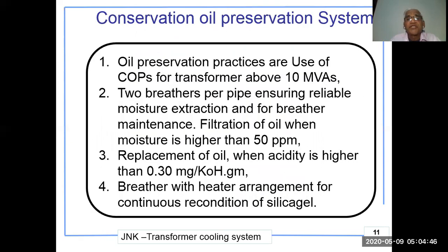Conservator oil preservation practices are used for transformers almost above 10 MVA, with breather pipes ensuring reliability. Key maintenance thresholds include: moisture filtration of oil when moisture is higher than 50 ppm, and replacement of oil when acidity is higher than 0.3 mg KOH per gram. A breather with heater arrangement allows for continuous reconditioning of the silica gel.